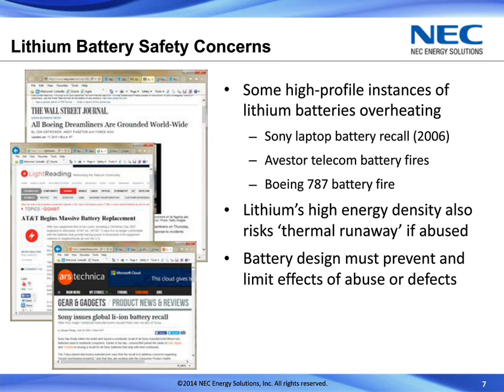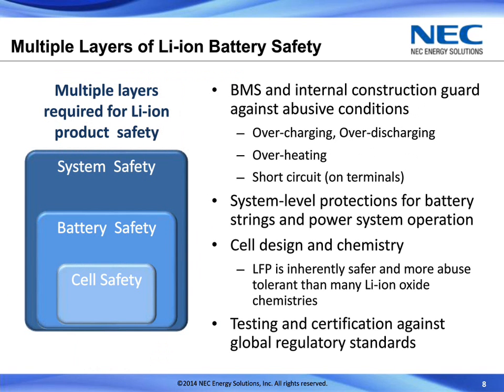So the real key here is, battery design for lithium-ion must prevent and limit the effects of any of these abuse, to prevent the kind of abuse or defects from occurring, and find ways to contain those situations if something does go wrong. So the approach to battery safety for lithium-ion is to really look at it in a multi-layer way. At the first level, at the battery level, and a battery is a combination of different cells, the battery management system and then internal construction techniques really have to guard against putting any cell into any kind of serious condition that would cause it to fail in a bad way.